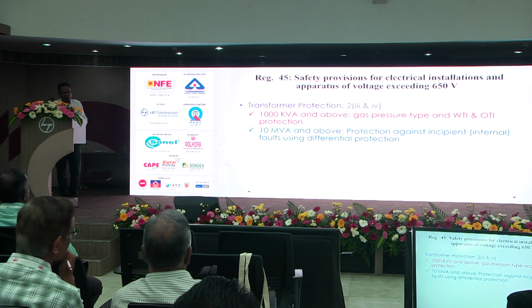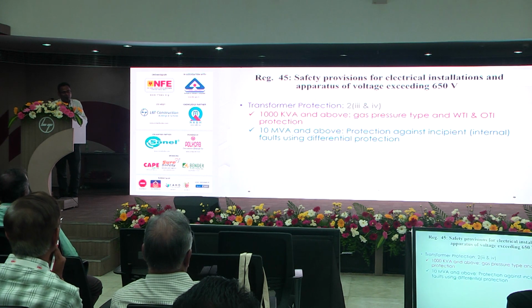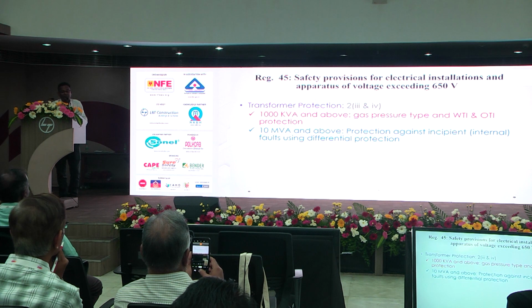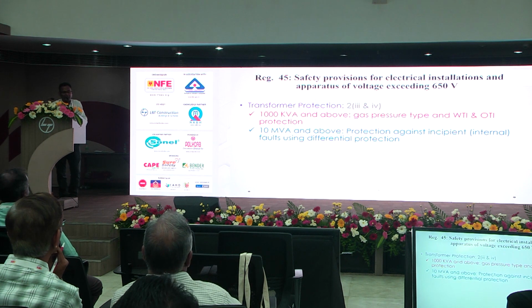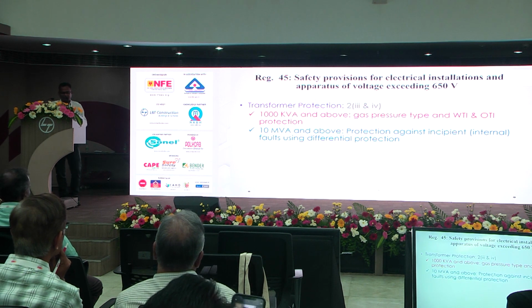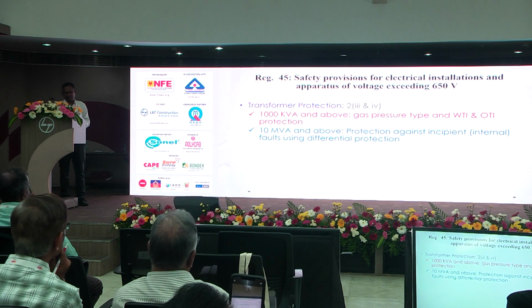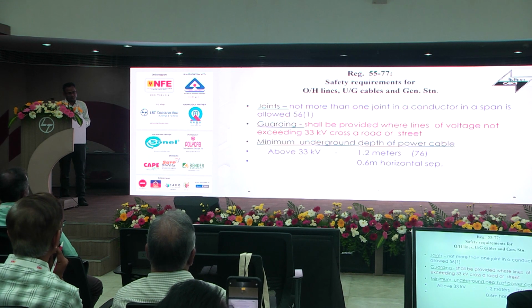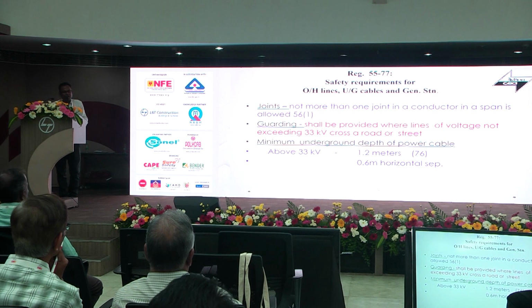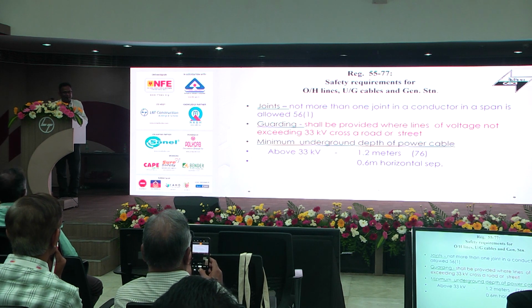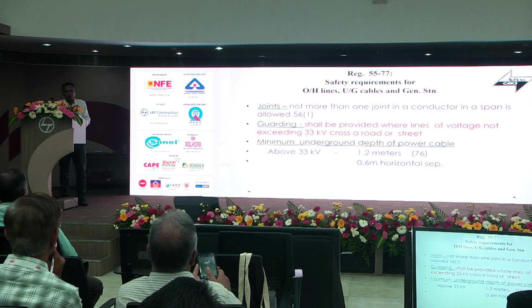And for transformers of 1 MVA and above, you have to use gas pressure type protection and Buchholz relays. For 10 MVA and above, differential protection is used to isolate the transformer in case of any incipient faults. There should not be any joint within one span in the case of transmission lines. So guarding should be there.